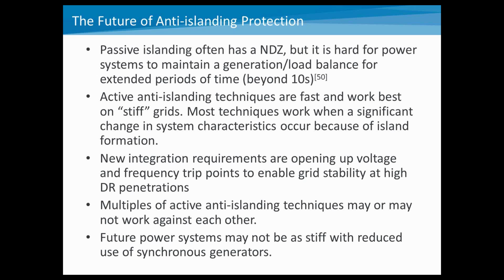One of the challenges we see coming up in the future is that new integrations are opening up voltage and frequency trip points to enable grid stability at high DR penetrations. So as you get more DR online, you may want to start opening up voltage and frequency trip points to maintain overall stability of the system. So how does that mesh with unintentional islanding requirements?